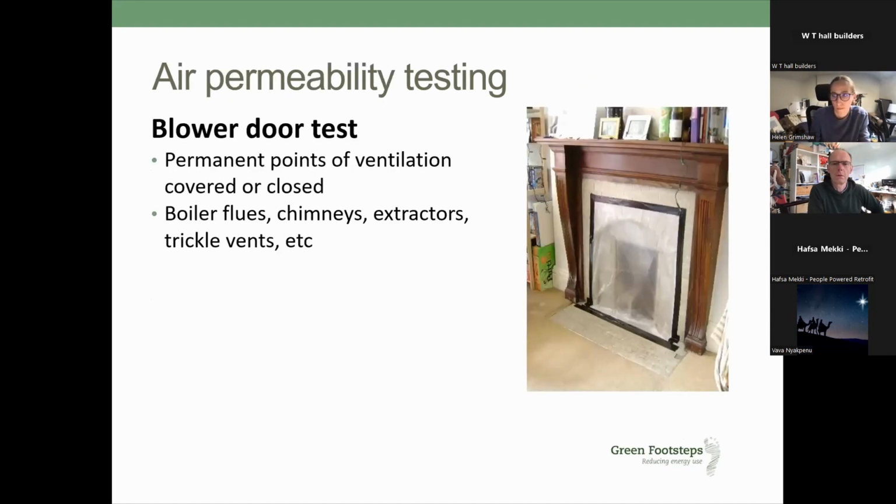The blower door test excludes deliberate points of ventilation. When you're talking to clients, they need to bear those extra points in mind, because in reality they are going to affect the energy use of the building. I've had instances of clients wanting to retain open fires in a building where they're putting shed loads of insulation in.